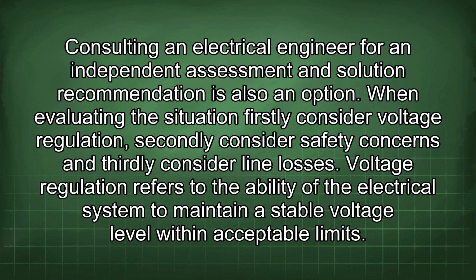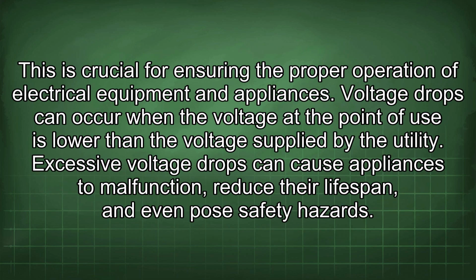Voltage regulation refers to the ability of the electrical system to maintain a stable voltage level within acceptable limits. This is crucial for ensuring the proper operation of electrical equipment and appliances. Voltage drops can occur when the voltage at the point of use is lower than the voltage supplied by the utility. Excessive voltage drops can cause appliances to malfunction, reduce their lifespan, and even pose safety hazards.